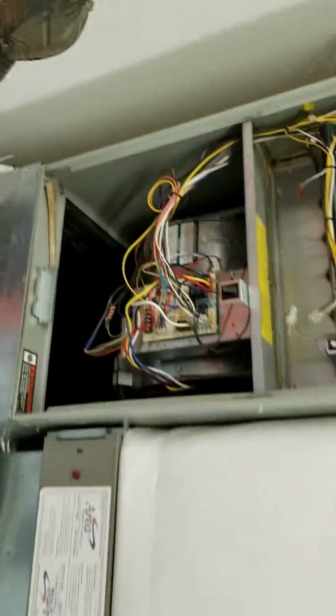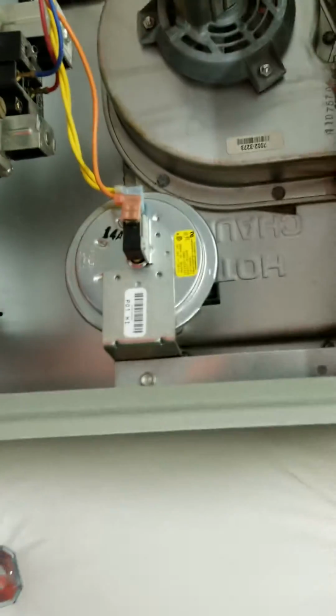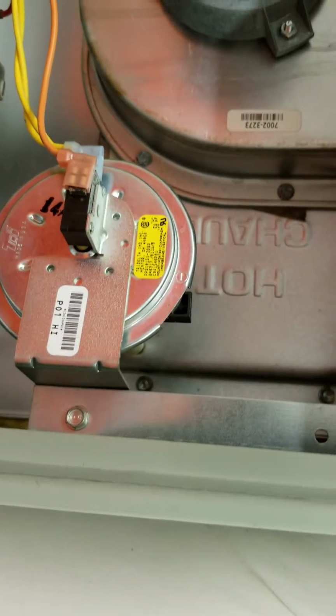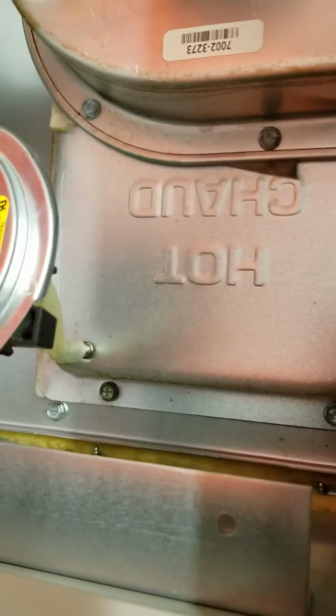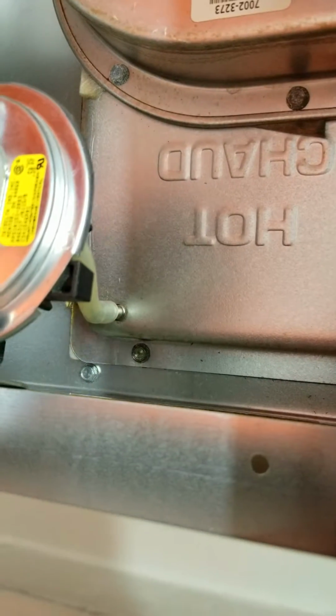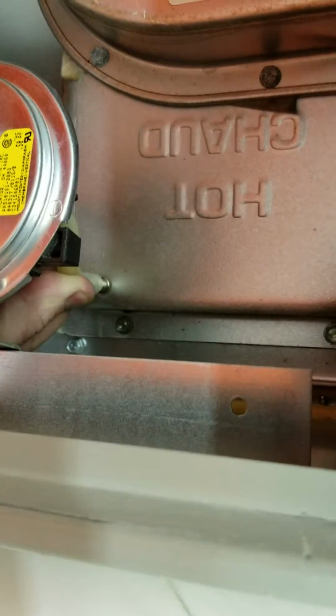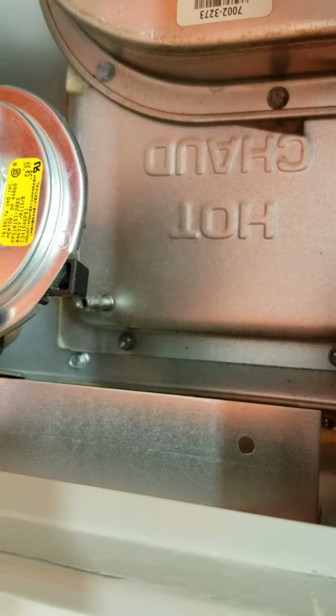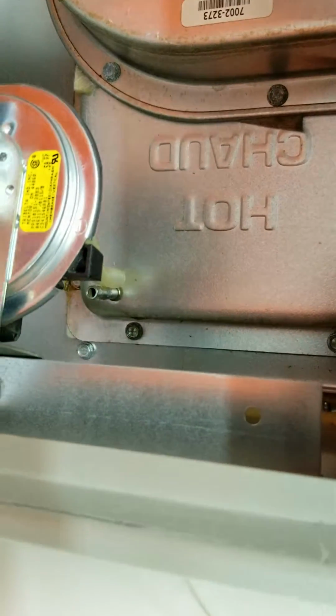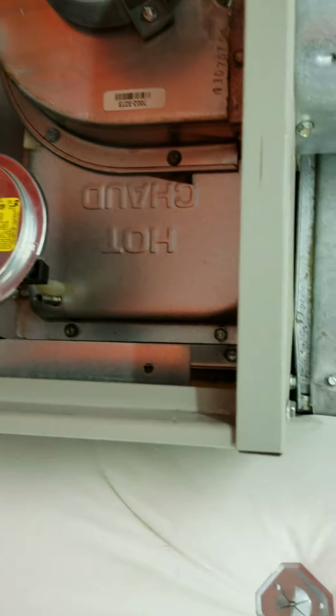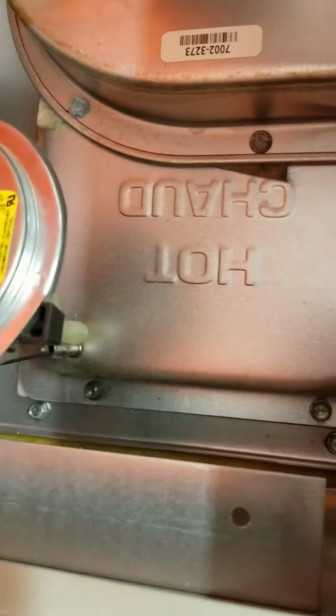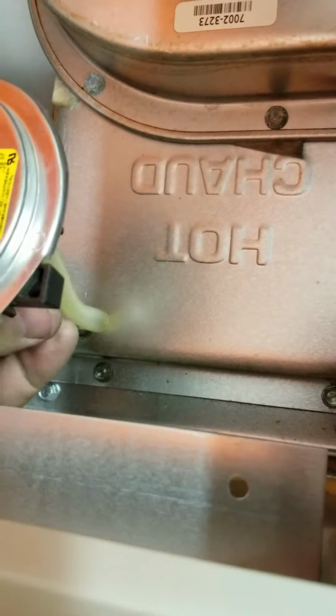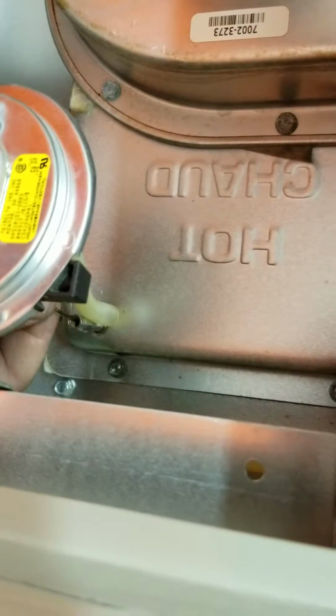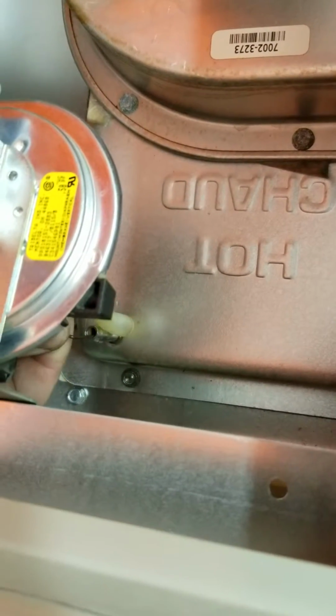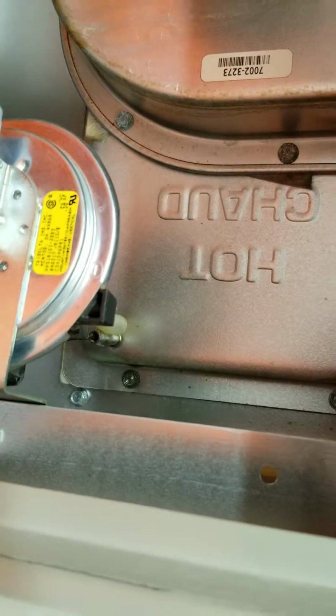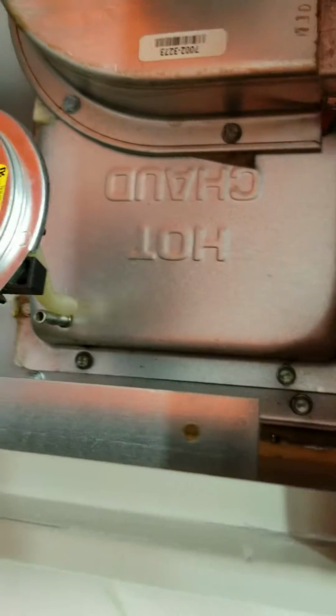Okay. Now, the next thing we're going to want to do is come up to the top part, the burner compartment, and right behind here you'll see that little port. That's the pressure switch port. That's what senses the draft. So what you'll want to do is pull the tube off of that and clean that with a rod, a piece of wire. Paper clip makes a pretty handy tool too. In this case, we're using a small Allen wrench. And make sure that there's no debris in that, because if that plugs up, your furnace again will shut down on the safety switches as it should.